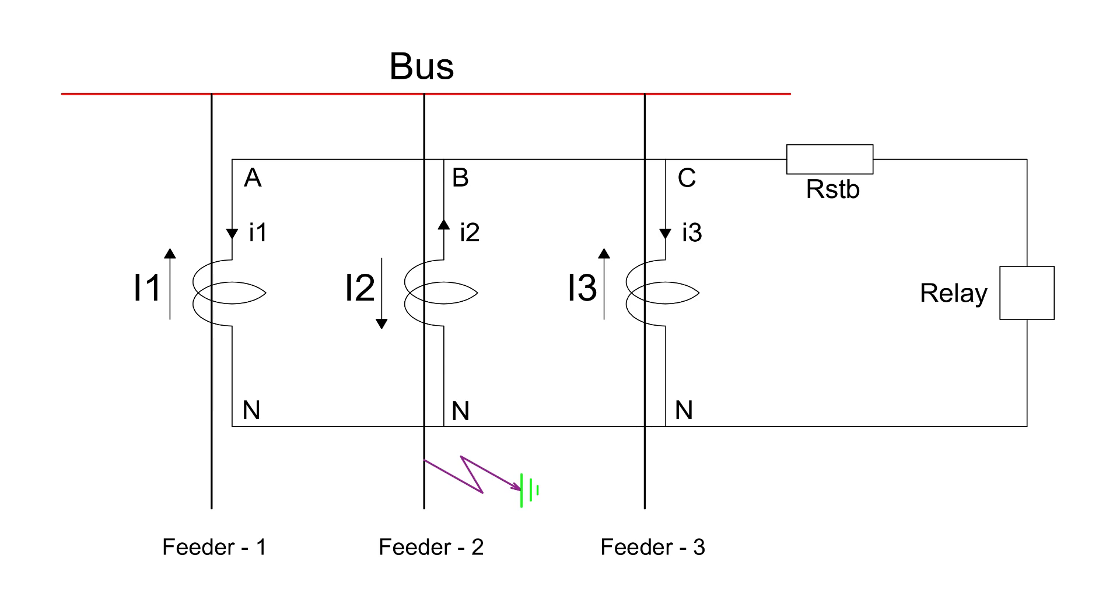When this happens, it no longer behaves as a current source, but rather acts as a resistor equal to the CT secondary winding resistance. As a result, the fault current does not flow towards the relay, but instead circulates within the saturated CT's secondary winding because current always follows the path of least resistance.